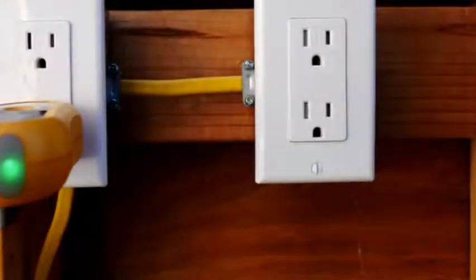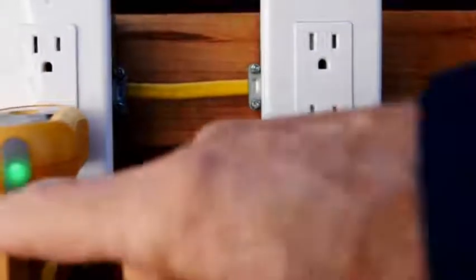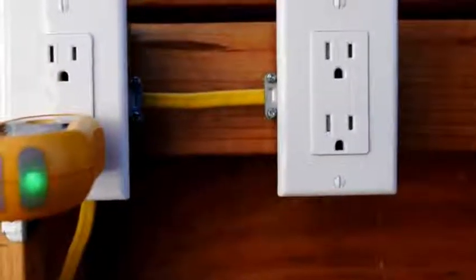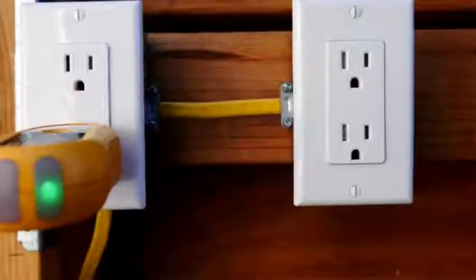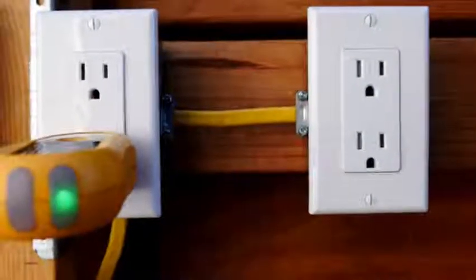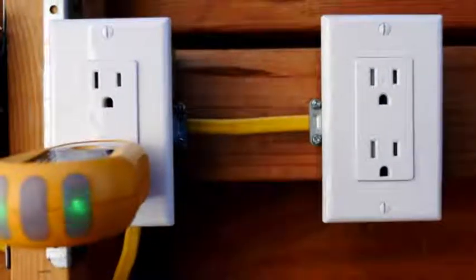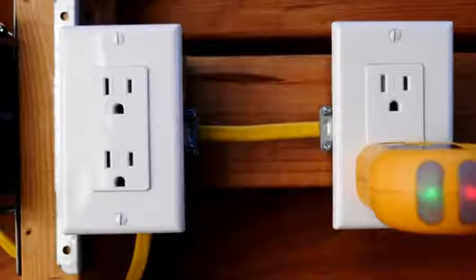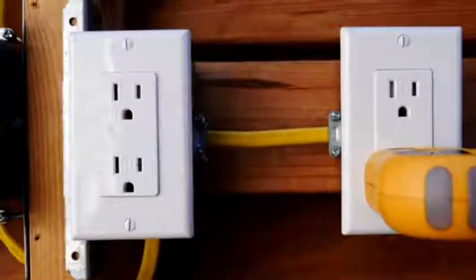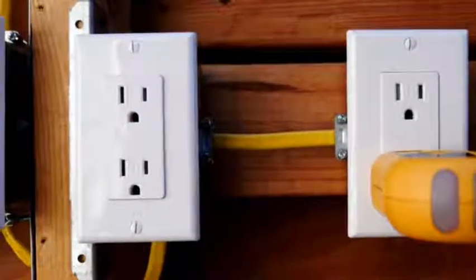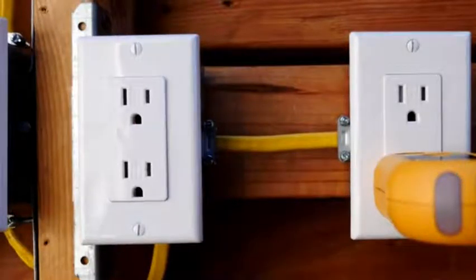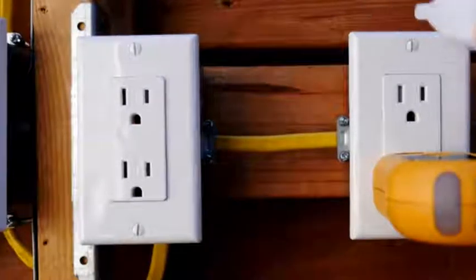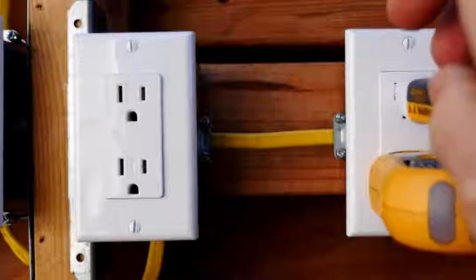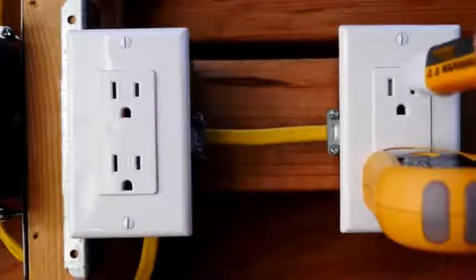It is a very good idea to also test other receptacles that are on the same circuit to see if they're wired correctly, because there is a situation where the entire circuit or several receptacles in a circuit can be reverse polarity. Okay, now I'm going to turn off the circuit breaker. The circuit breaker is off, and our outlet tester is indicating that the circuit breaker is off. But I'm also going to test with my voltage detector, and it agrees that the circuit is off.